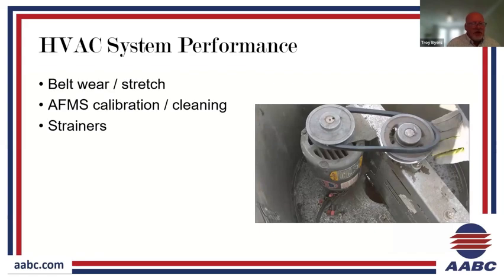And so other areas that require periodic maintenance and are identified in existing buildings when we do existing building TAB is flow measuring station calibration. A lot of these flow measuring stations start to pick up lint or particulate, and they need to be cleaned so that they can be calibrated. Strainers. This is another area where if they're not cleaned periodically, we're going to start building up a lot of resistance in the system, or maybe have coils that just are not receiving the design water flow due to some clogged strainers. That could also apply to our pumps as well, right?